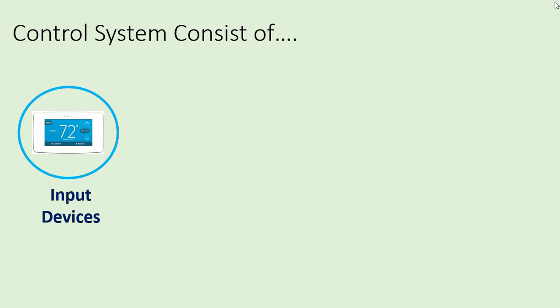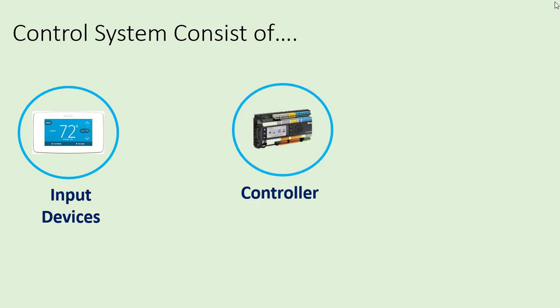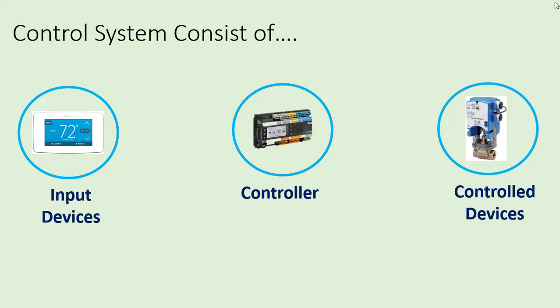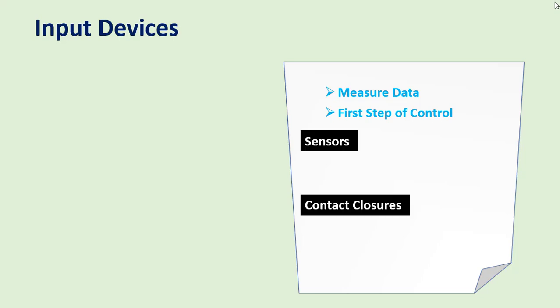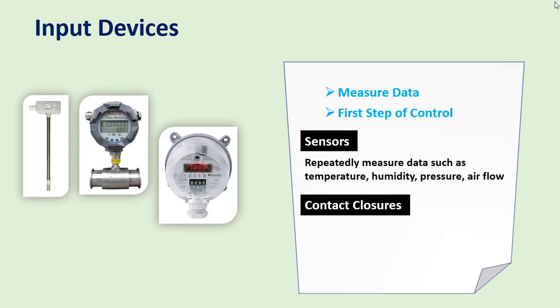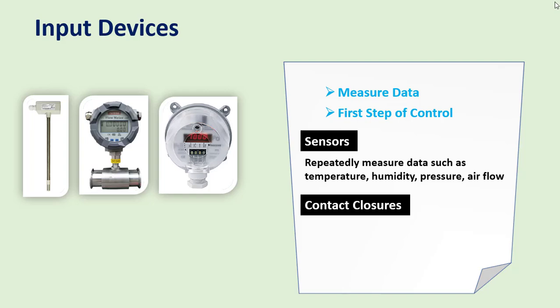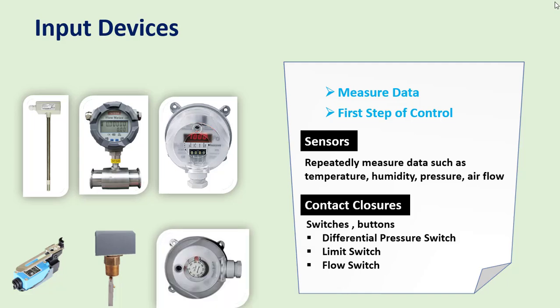A control system consists of input devices, a controller, and output devices — also known as controlled devices. Input devices measure data and are the first step of control. These can be sensors and contact closures. A sensor repeatedly measures data such as temperature, humidity, pressure, and airflow, while contact closures are switches and buttons. Examples include differential pressure switches, limit switches, and flow switches.